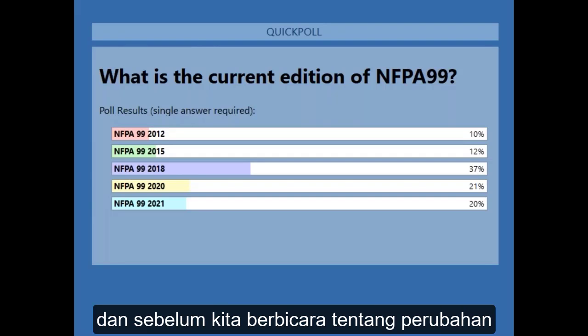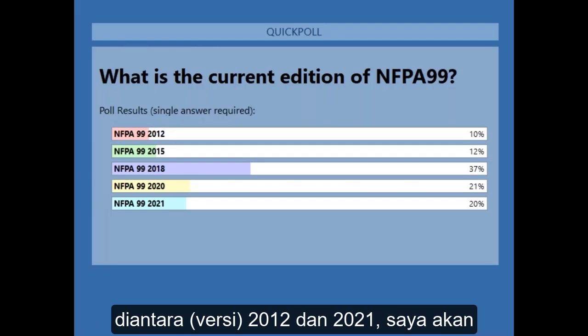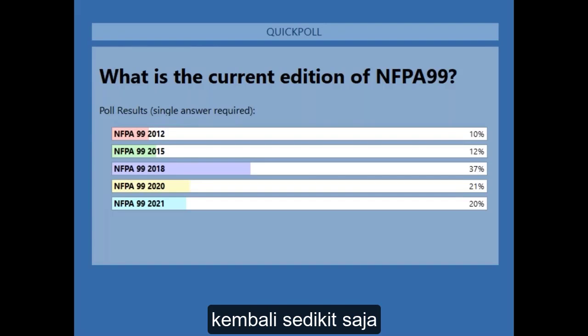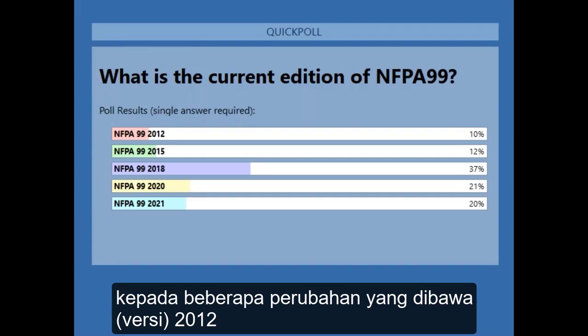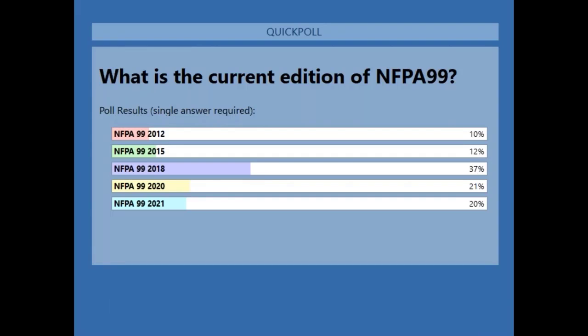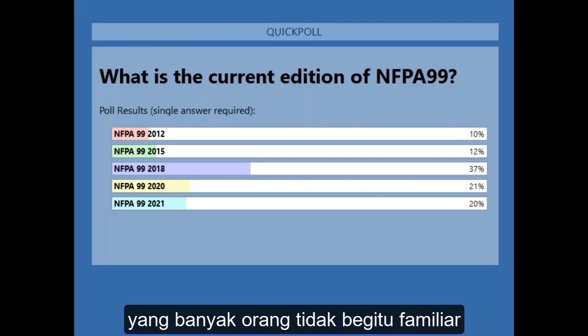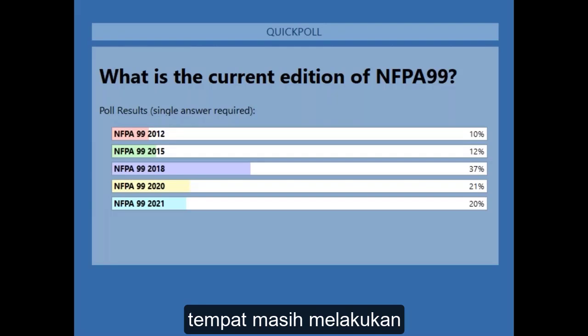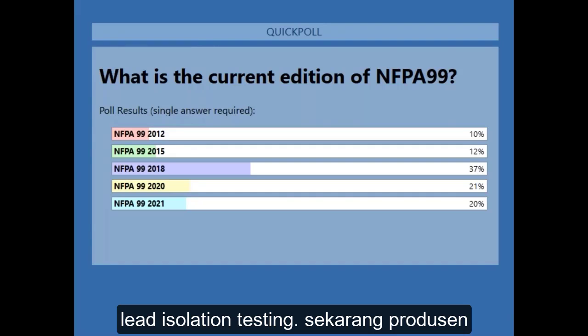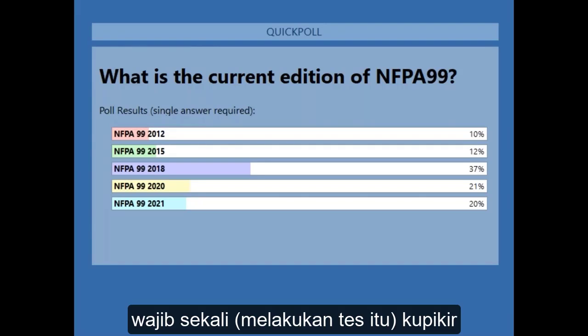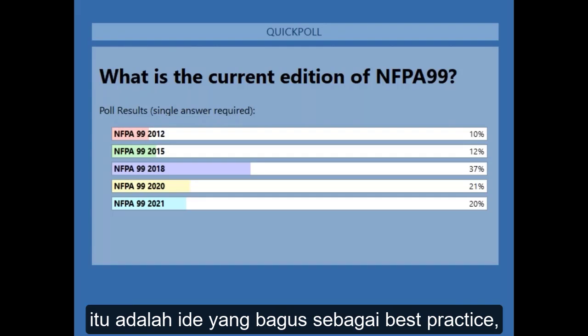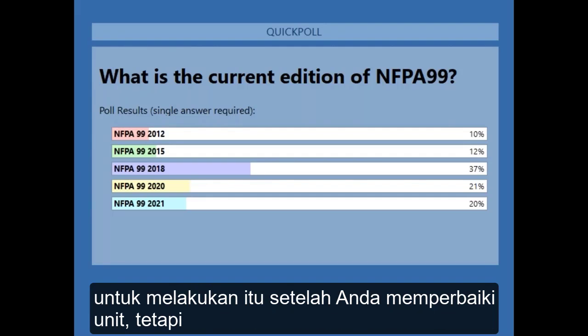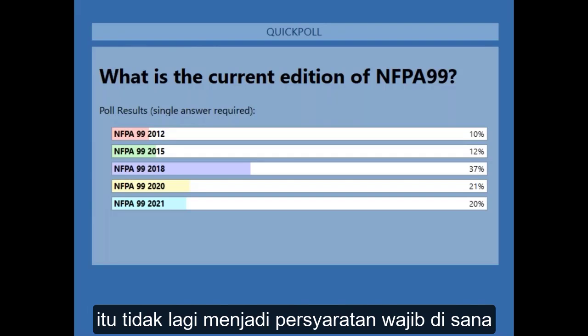And before we talk about the changes between 2012 and 2021, I'm going to go back just a little bit to some of the changes that 2012 brought upon that a lot of people are not familiar with. One of the things in there, a lot of places still do lead isolation testing. Now, manufacturers absolutely are required to. I think it's a good idea, the best practice, to do it after you've repaired the unit, but that is no longer a requirement in there.